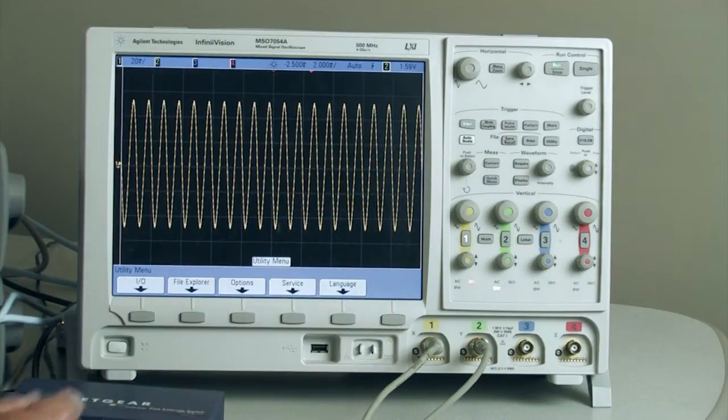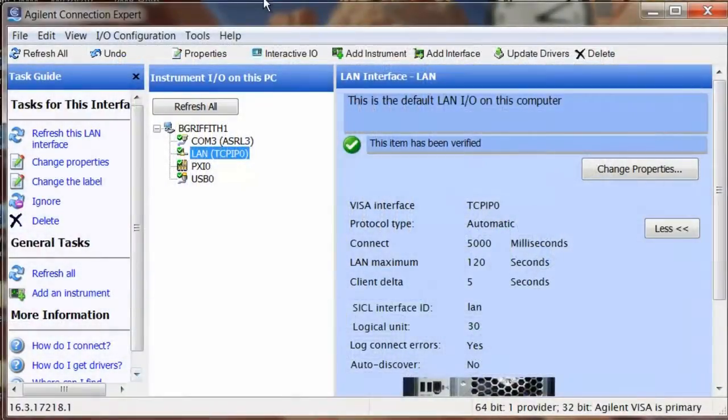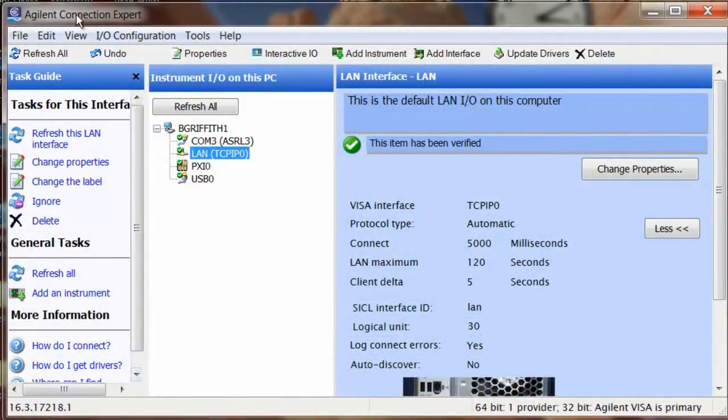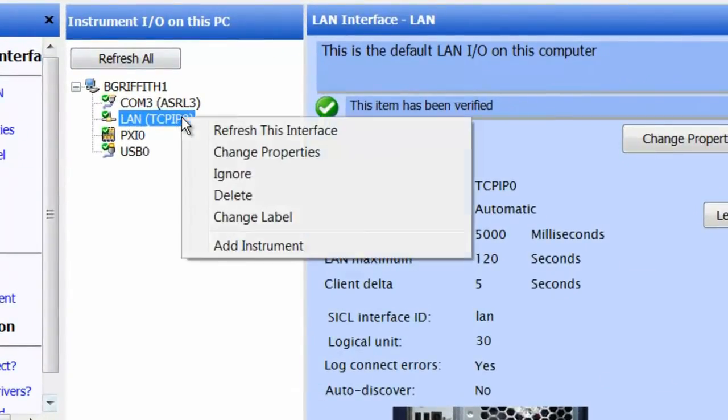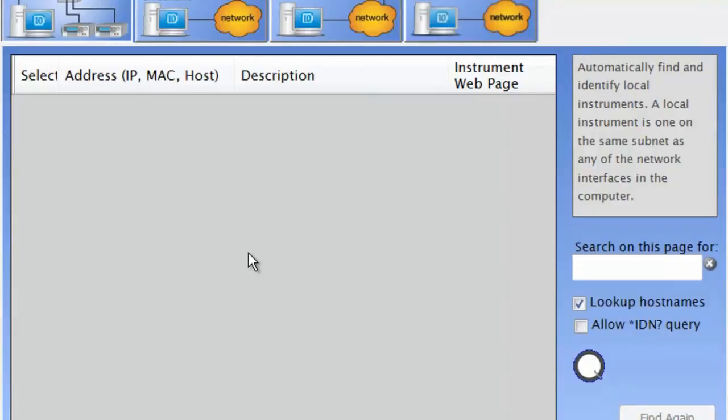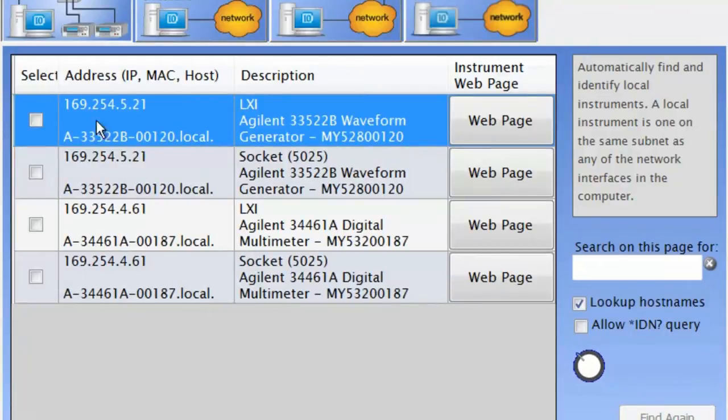Once we've reset all of our instruments, we can then go to the PC and we'll use the Agilent Connection Expert. And we'll go ahead and find each of our instruments on the LAN. So it's going out and discovering each of the instruments on the LAN interface. So it discovers the instrument and it also discovers the socket interface for each of the instruments as well.